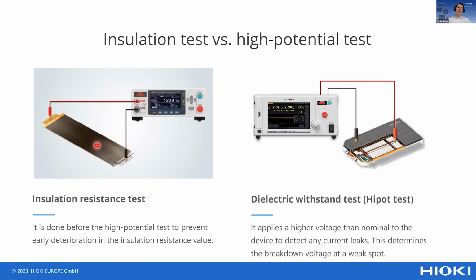And typically, this test is being done with a high potential in order to identify if there is already any deterioration happening with the insulation. So the insulation resistance value is the most interesting parameter you want to get out of that. While when you do a dielectric withstand test, you want to understand if you have any current leaks. Or alternatively, also from a safety point of view, you also want to understand at which applied level of voltage there will be a potential breakdown of the device. So these are the 2 main different applications, cell versus final pack or module.